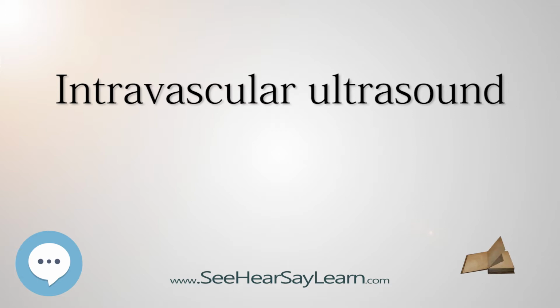The sound waves are emitted from the catheter tip, are usually in the 20 to 40 MHz range, and the catheter also receives and conducts the return echo information out to the external computerized ultrasound equipment, which constructs and displays a real-time ultrasound image of a thin section of the blood vessel currently surrounding the catheter tip, usually displayed at 30 frames/second. The guide wire is kept stationary and the ultrasound catheter tip is slid backwards, usually under motorized control at a pullback speed of 0.5 mm/s. The motorized pullback tends to be smoother than hand movement by the physician.